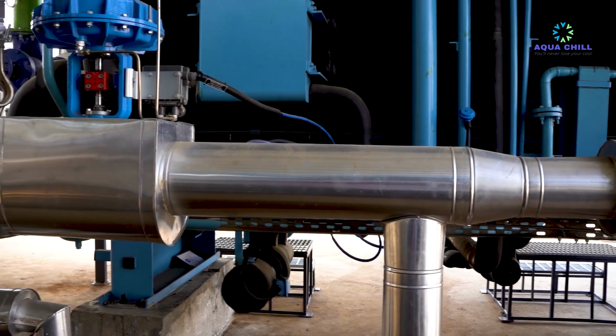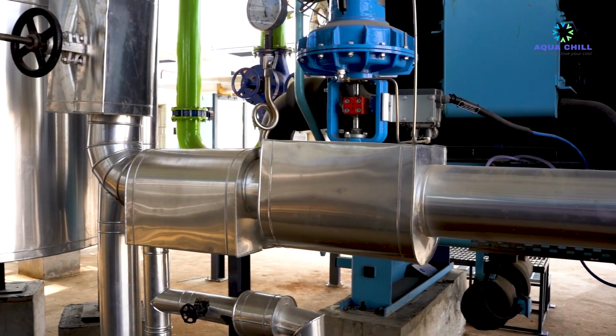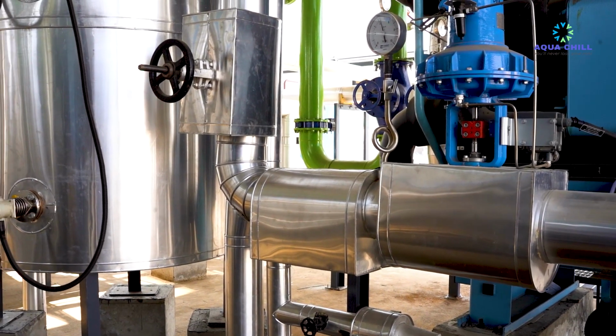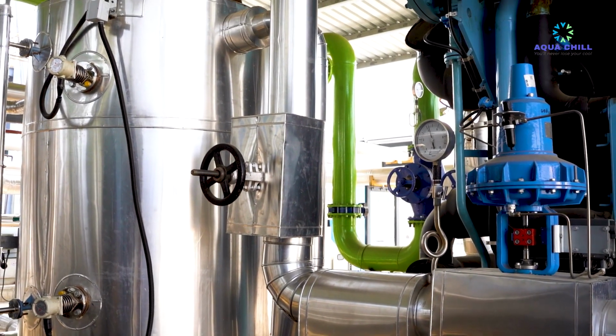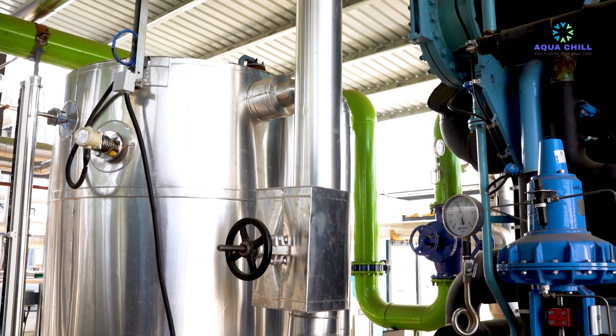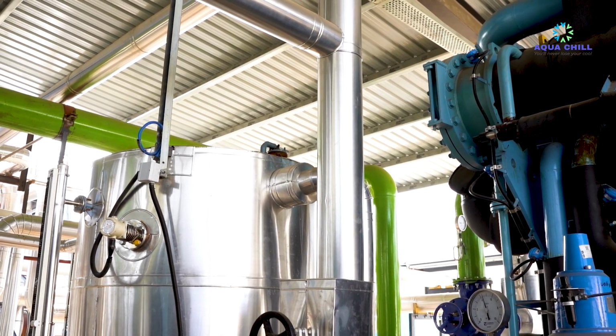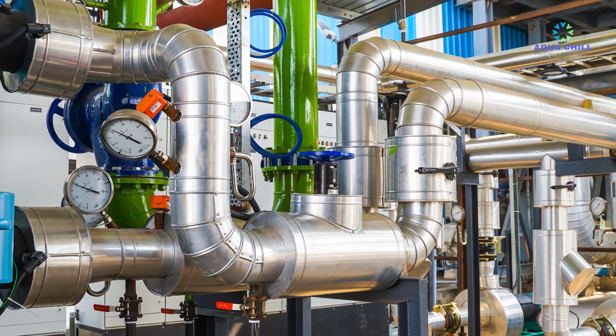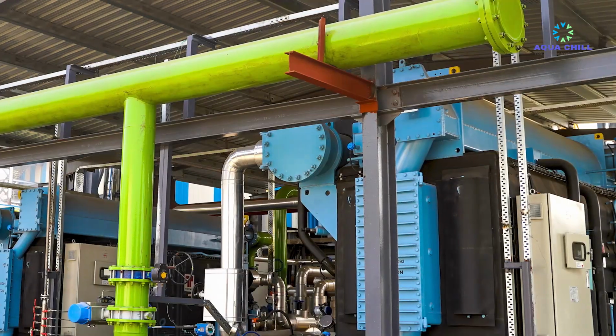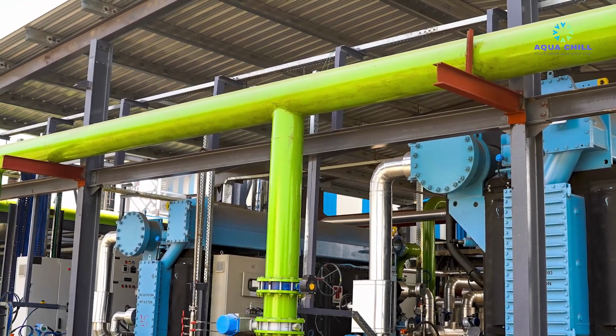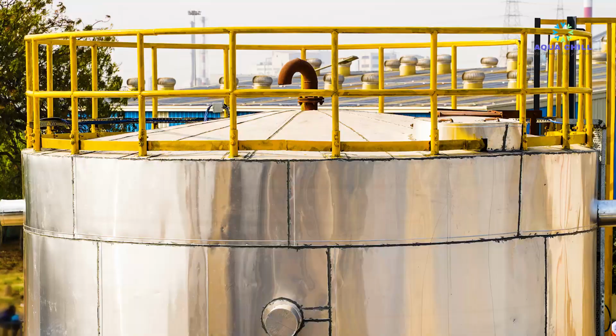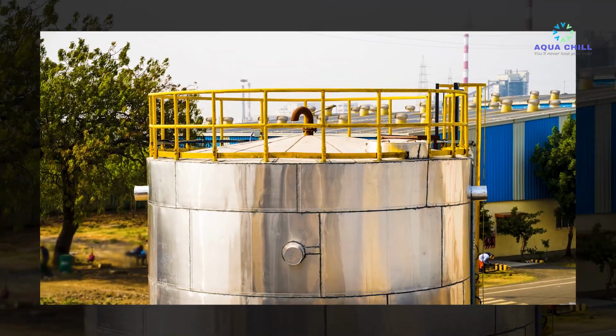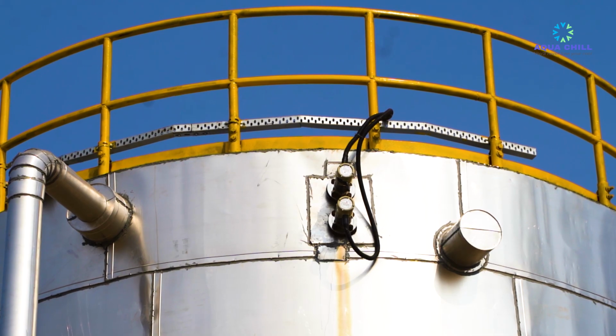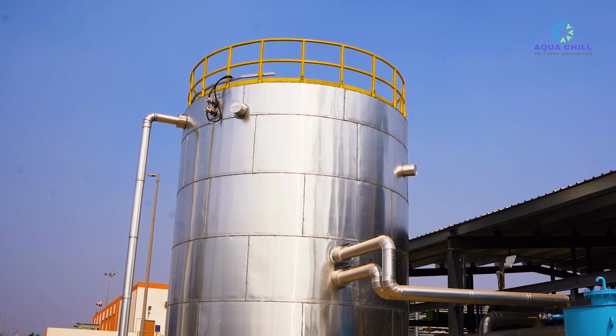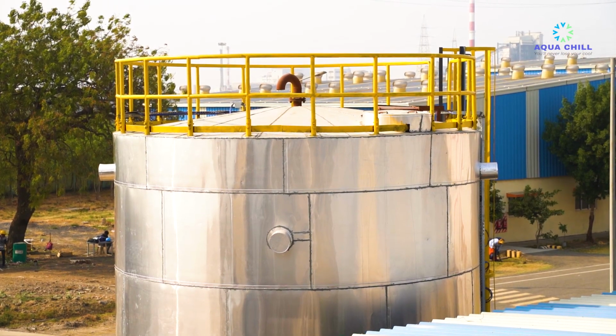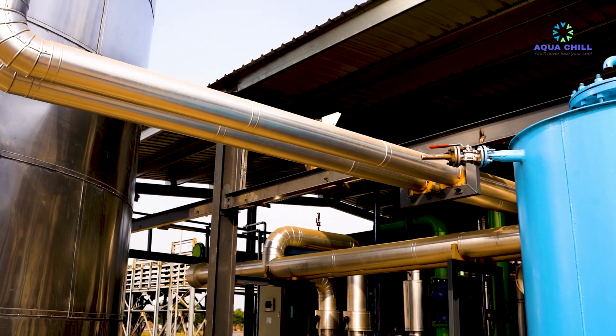The third and equally critical challenge was that the surplus steam available from the recovery project was not sufficient to address the peak cooling demand of the suction air cooling through the absorption chiller. The quantity of steam available was able to address only up to 70% of the peak cooling demand of the suction air. Here, Aqua Chill came up with this highly innovative idea of using a thermal flywheel in the system. This was done based on harnessing the benefit of substantial variation in the hourly cooling load, even in peak season.